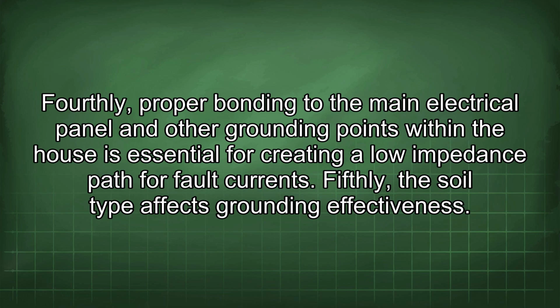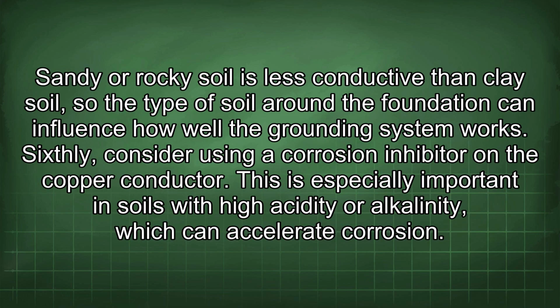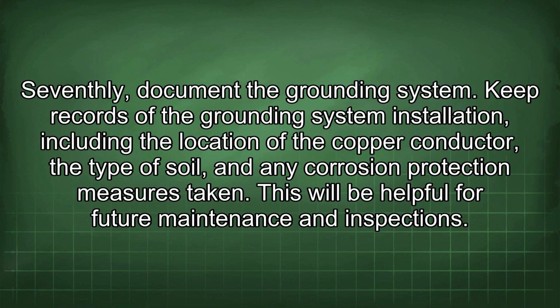Fifthly, the soil type affects grounding effectiveness. Sandy or rocky soil is less conductive than clay soil, so the type of soil around the foundation can influence how well the grounding system works. Sixthly, consider using a corrosion inhibitor on the copper conductor. This is especially important in soils with high acidity or alkalinity, which can accelerate corrosion. Seventhly, document the grounding system. Keep records of the grounding system installation, including the location of the copper conductor, the type of soil, and any corrosion protection measures taken. This will be helpful for future maintenance and inspections.